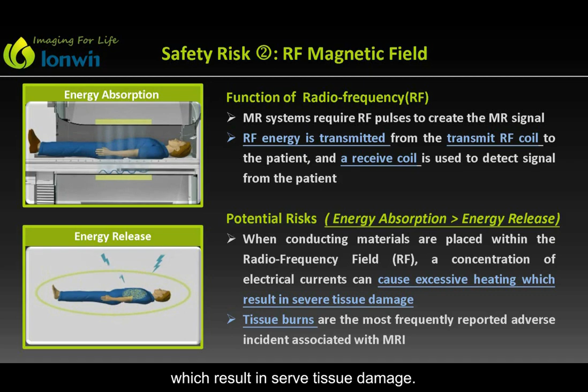Throughout the procedure, the patient has energy absorption, and at the same time, energy release is going on. The potential risks happen when energy absorption exceeds energy release. It means that the excessive energy can be deposited in the body. Sometimes it can cause excessive heating, which results in severe tissue damage. Here is an example of an MRI radiofrequency thermal burn where amputation was required.